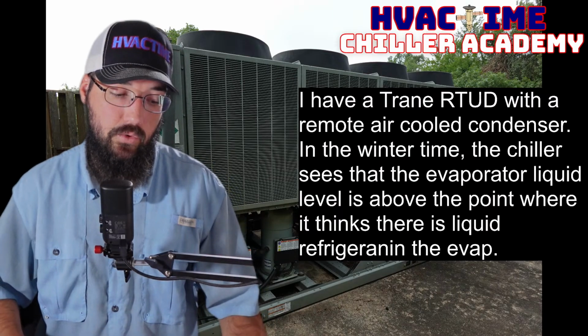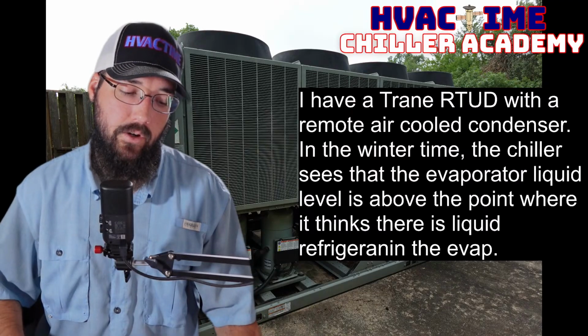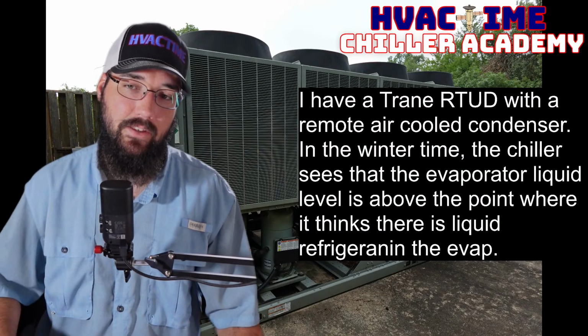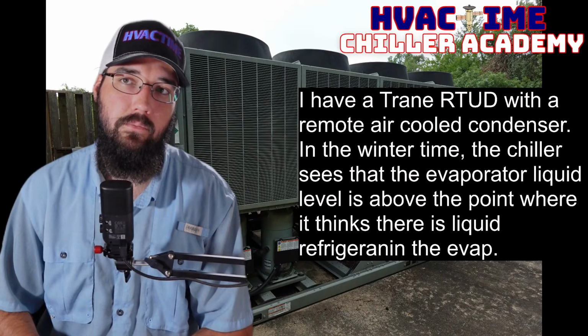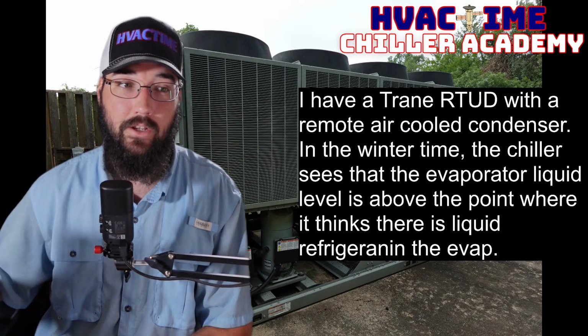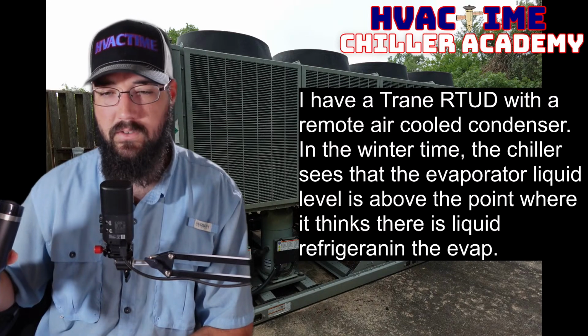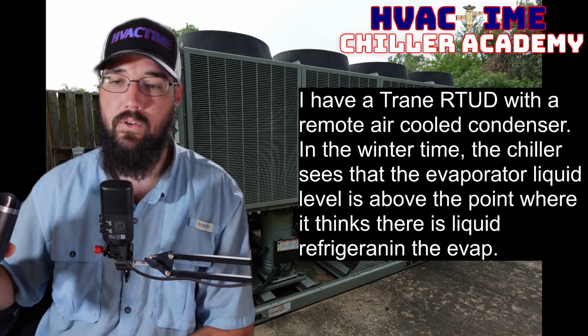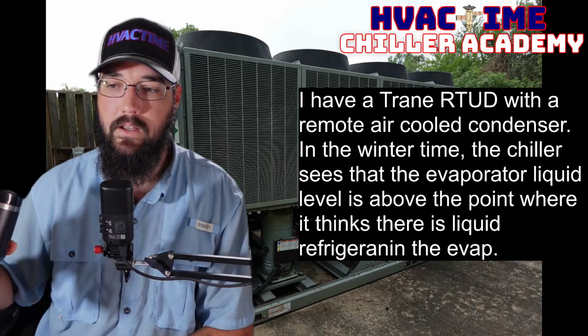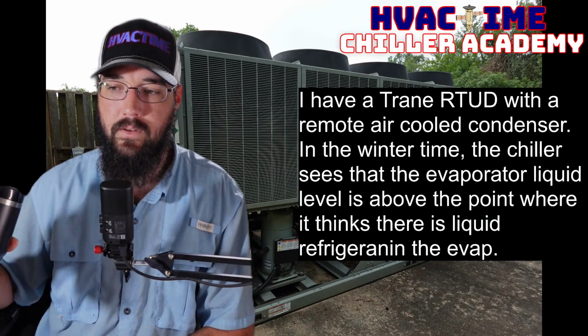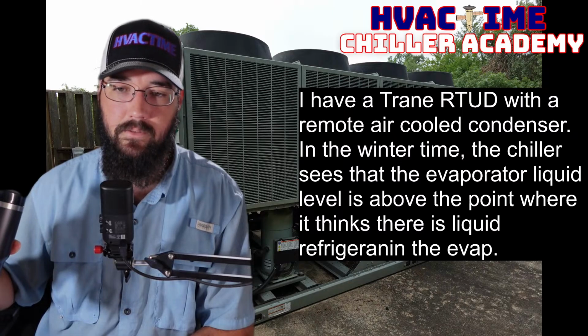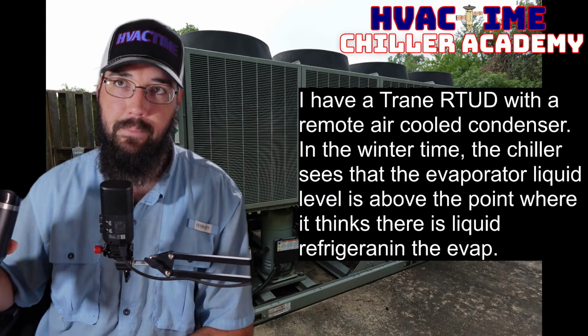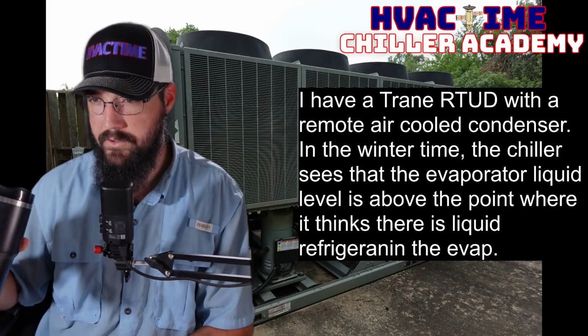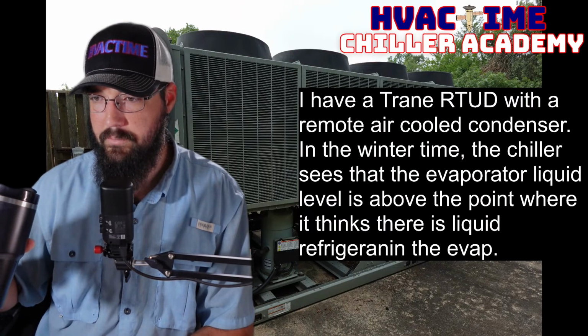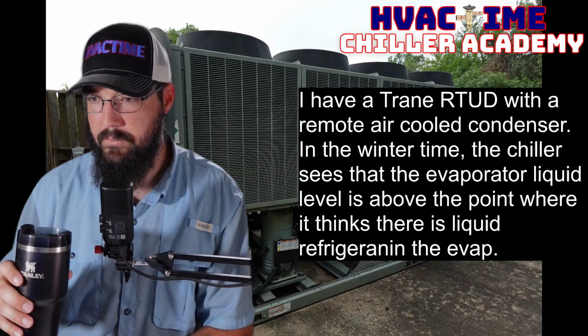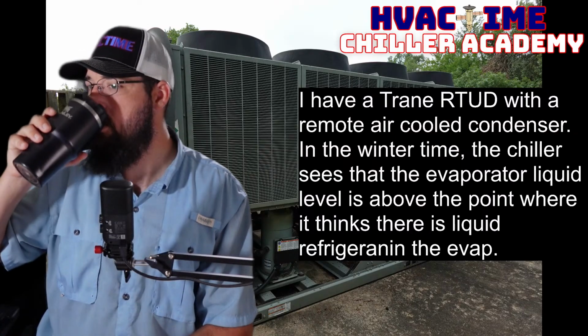Because these machines do have trouble where when they do start oil stacking in the evaporator, especially on the older style sensors. I know they changed the style of sensor to address this, but the older sensors really struggled with being affected by the foaming that happens with the additional oil charge in the evap. So the chiller is pumping down because of low ambient temps to move the refrigerant out of the evap. Yeah.